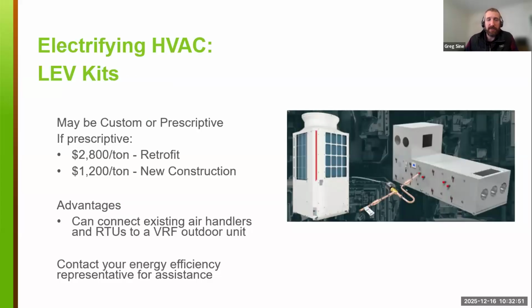This is LEV kits, so LEV stands for linear expansion valve. Basically, it's a component of an air handling unit or heat pump system. These kits allow us to retrofit newer rooftop units or air handling units with a heat pump coil, which is served by a heat pump outside condensing unit. A scenario where I could see this being a good fit would be, for example, if you had to replace an air handler or RTU in an emergency situation and weren't able to select a hybrid heat pump RTU because you needed something in the immediate term, off the shelf. We could go back later and retrofit that unit with a heat pump coil to help decarbonize the space served by that equipment.